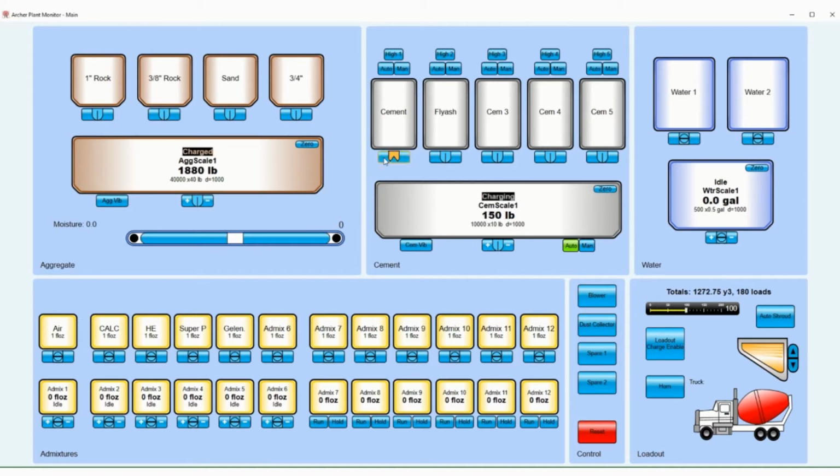Material fills are usually designed with an open delay, so the action of opening a gate or valve manually will not be immediately apparent. This menu shows the different states and styles of the buttons. The discharge buttons are similar in graphic design to their fill button counterparts. These buttons have two distinct regions denoted with a plus and minus symbol, and are therefore really two different buttons. The left plus button opens the gate or valve, whereas the right minus button closes it.